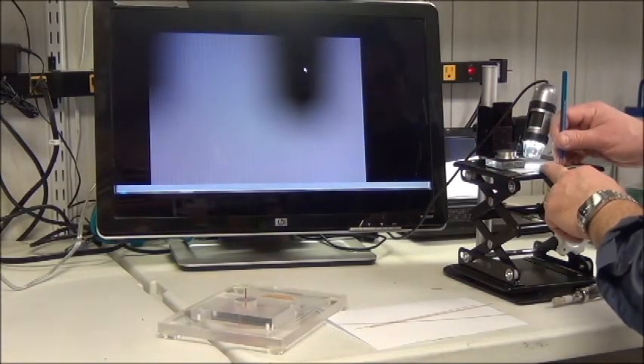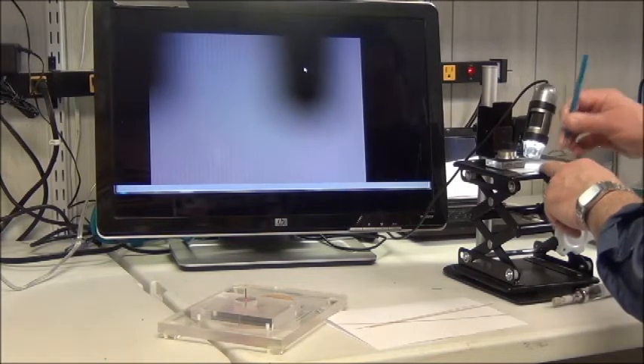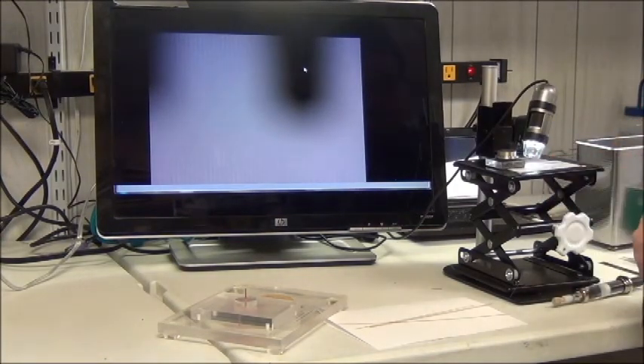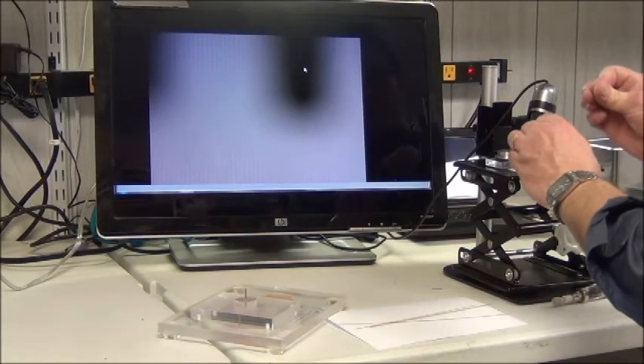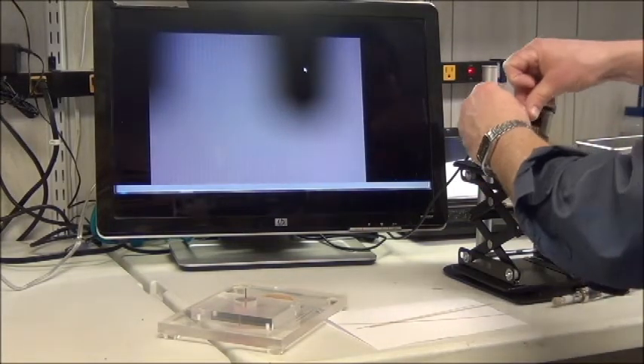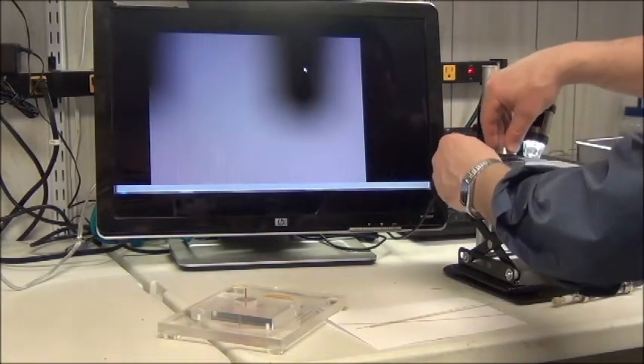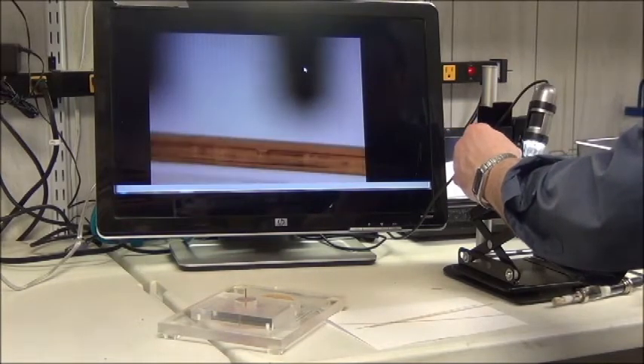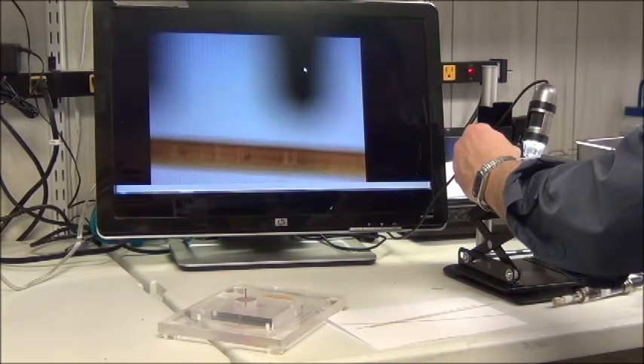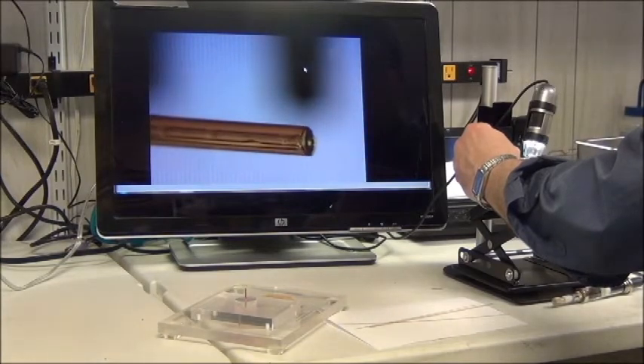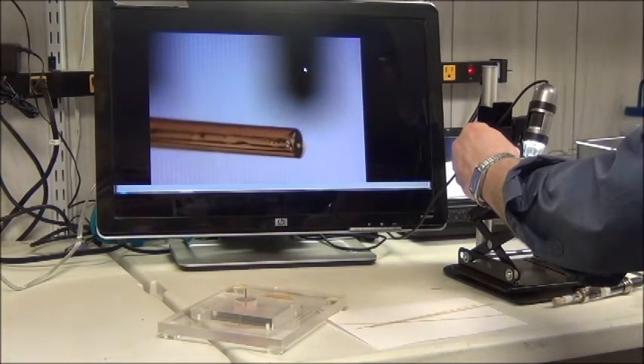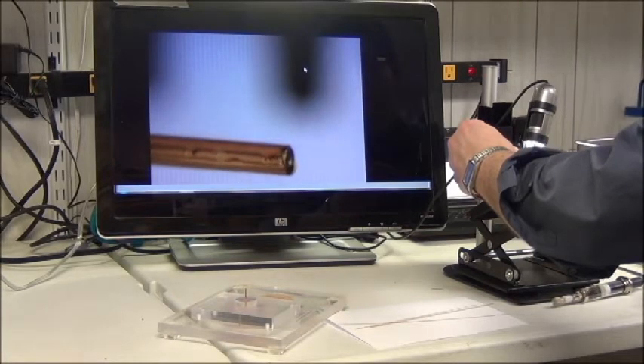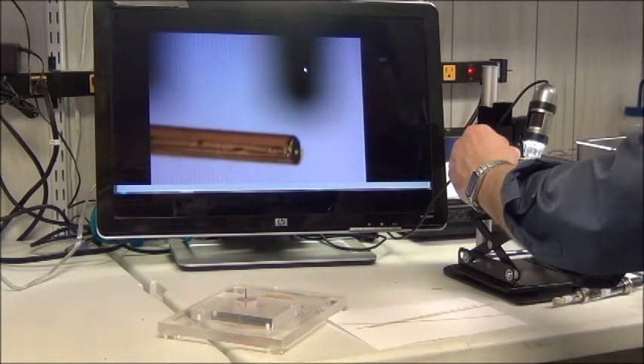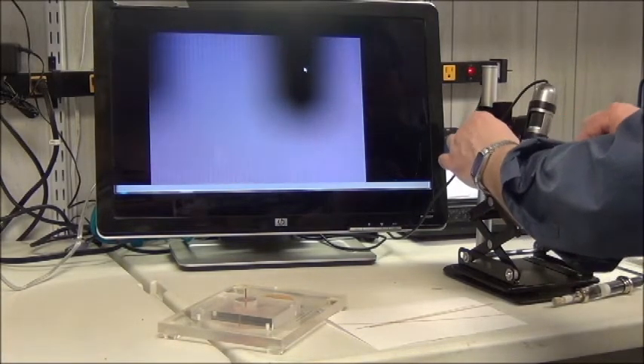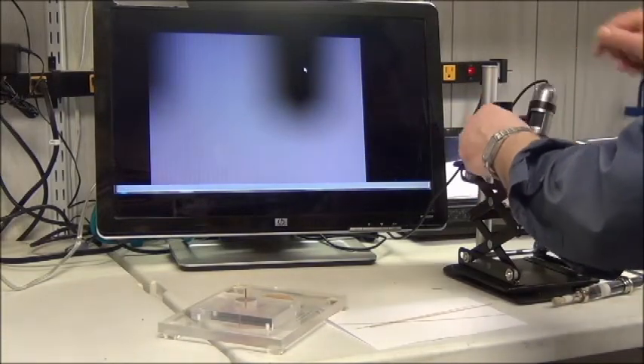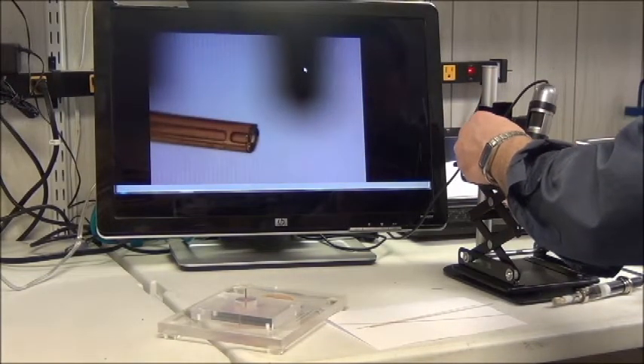So here, I'm just going to touch a little bit, and pull the glass capillary tubing straight apart. Let's examine those ends. That's actually a pretty good cut, as you can see. That's pretty straight. The polyimide is just a little bit off. The other side should be just about as good. Yeah, it doesn't look bad at all.